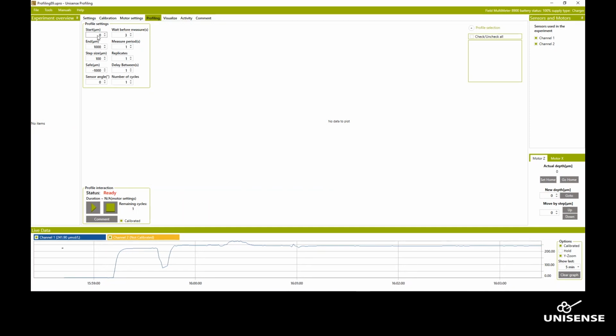In this case, I would like profiles to start at 0. I think I will let it go to 4 millimeters or 4,000 micrometers. For the first profile, just not to waste too much time, I will go in at 250 micrometers at a time, so a quarter of a millimeter. The safe distance is the position where the software will park the sensor after the profile has been finished. I will just put it to 0 because I'm operating it and I know where the sensor is. If you are leaving it and want to come back after an hour or tomorrow, it may be smart to park it up high away from any animals that could be in there. I think I would like to measure for 5 seconds, wait 5 seconds before I do the measurement for 1 second. So now this is set up.